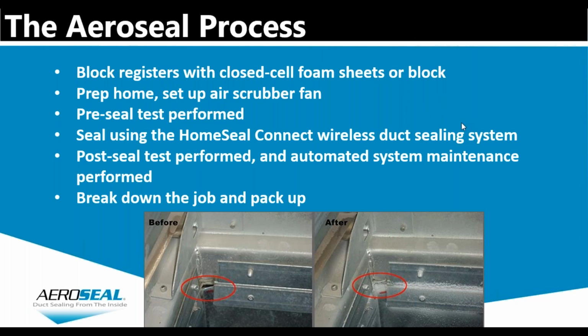You can see down here on the bottom left the before picture, and on the bottom right the after. The sealant is accumulated, or deposited, right at the leak point. There's a common misconception that Aeroseal encapsulates the duct. It's not an encapsulant that lines the ductwork with a lot of material or sealant. It just goes to the leak points.